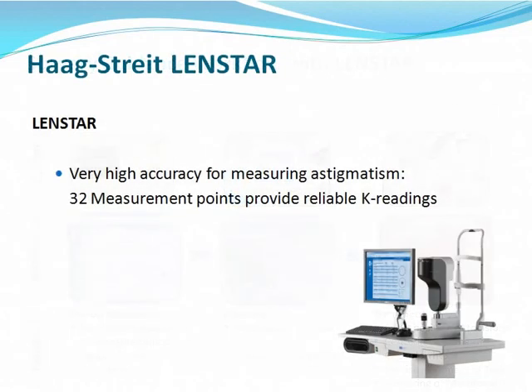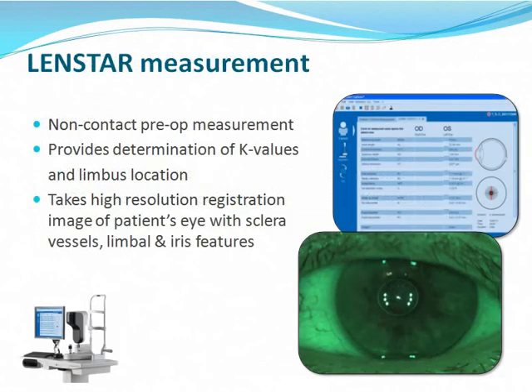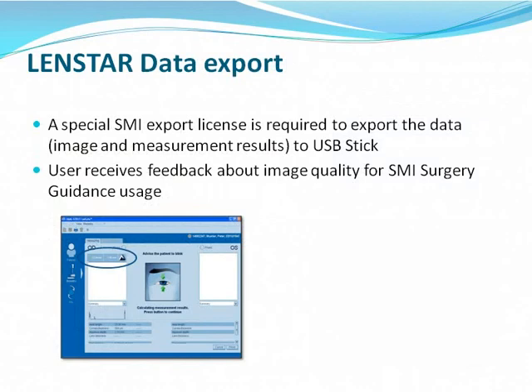The LENSTAR has very high accuracy for measurement of astigmatism because of the 32 measurement points available. It's a non-contact measurement that provides determination of K-values and limbus location. This high-resolution picture is combined with limbal vessel features and iris features. In the LENSTAR machine interface, there is a separate sheet where the SMI export button is indicated, and a license is required to export this data to a USB stick that is loaded into the surgery pilot.